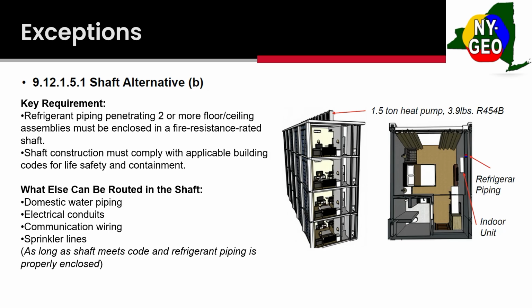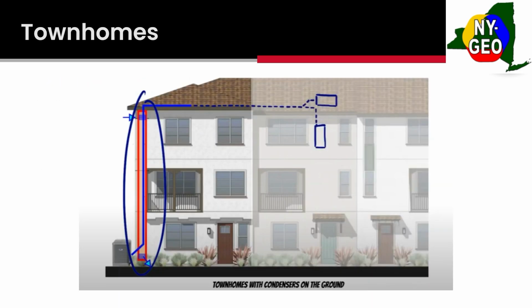So townhomes, do a lot of townhomes. When you're doing townhomes, or anytime you're mounting a condenser on the ground, run your refrigerants on the outside. That's the easiest way to ventilate them. But then when you go into the attic, where either your fan coil or your air handler is in the attic, or say you've got a high-rise system right there, there's no requirements. This does not need to be ventilated. It is an unoccupied space. Again, if you remember, let me back that up.